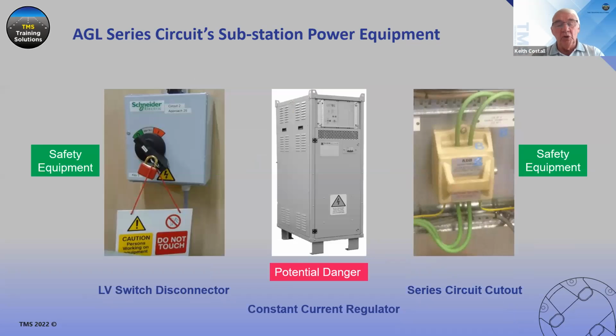This is what the equipment looks like. The incoming protected device, this is the safety equipment. We have the output disconnecting device, which connects between the CCR and the field. And this is one model. And of course, in the middle of this is the constant current regulator. They range in a whole range of sizes, from 2.5 kVA up to 30 kVA, traditionally in a 6.6 amp system. And at 30 kVA, when it's fully loaded, we could have 4,545 volts RMS.